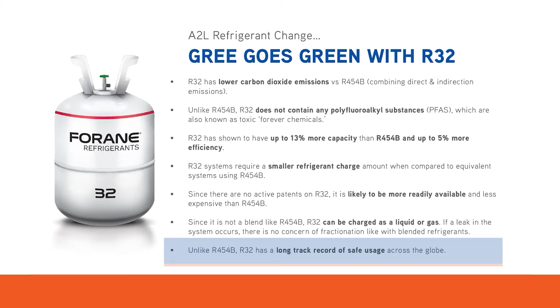However, what you have to know is most of these new low GWP refrigerants are known as A2L refrigerants. The A means it's low toxicity. If you see a B in that position, it means it is toxic. The 2 is more likely the sticking point for most people. The 2 means it is slightly flammable. So all of these new refrigerants coming out will most likely be flammable.